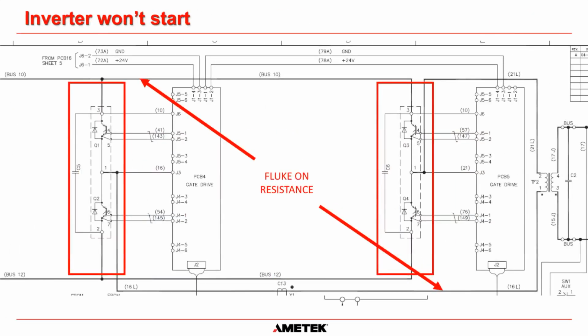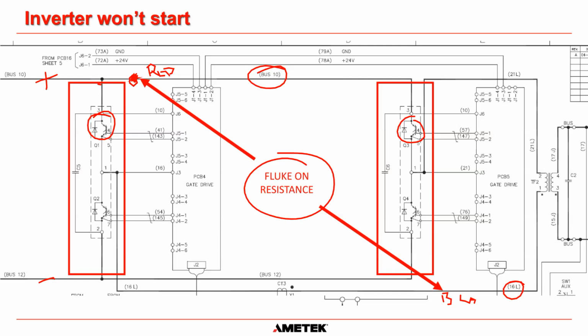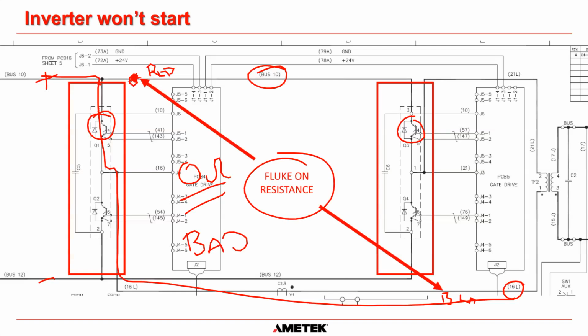And to check whether you have a bad IGBT, remember, this is positive, this is negative. There's also a very easy check when the system is completely de-energized. You can clip your Fluke on resistance. So clip your red lead to the positive bus, which is wire 10, and then connect your black lead to wire 16. And what you can see is if either of that IGBT or that IGBT fails, let's say Q1 has failed, if you follow it down, that will give you 0 ohms if there was a short on the IGBT. 0 ohms is bad. That means you have a bad IGBT. And this test checks Q1 and Q3, okay?